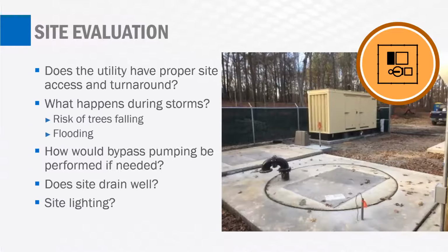Your pump station site may not have a permanent generator power there for backup power. You might have to bring that generator power in on trailers and hook up to provide power reliability that way. Well, what happens if you can't get those portable generators to the site? Sometimes when you're looking at these sites and you're questioning, okay, what kind of floods have occurred out here? You may not be able to simply rely on flood maps. This is where the O&M staff come into play again. The simple question, how high have you seen floodwaters at the site? And they can give you some good information that you may not be able to find elsewhere.